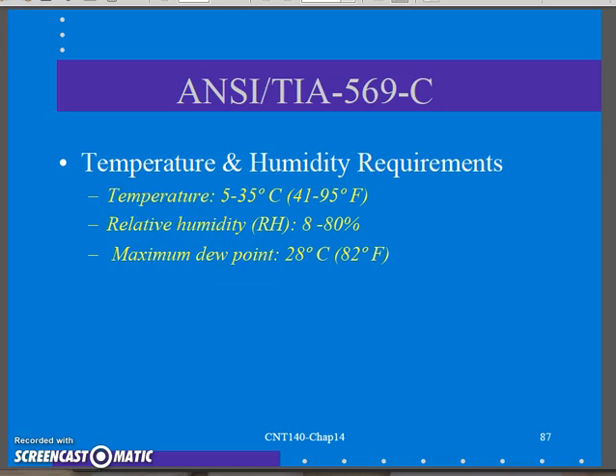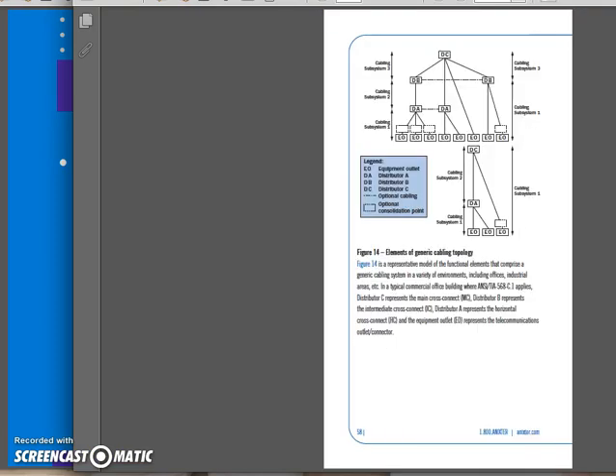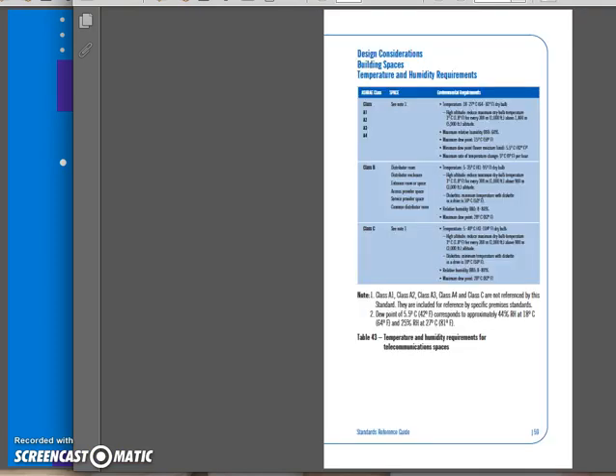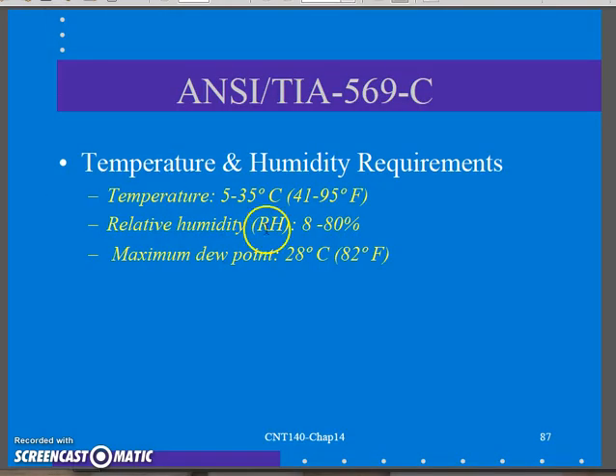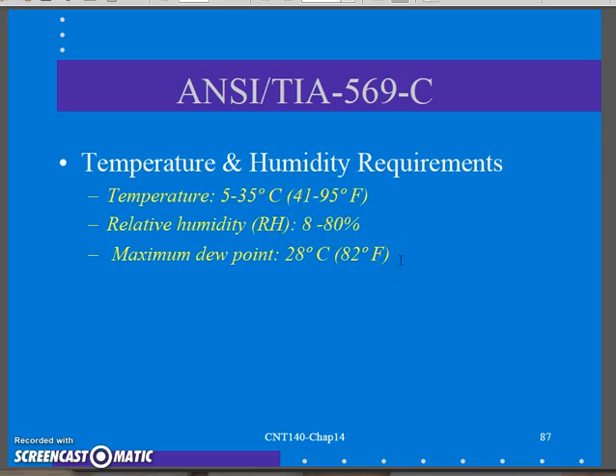One of the first things they mention in the standard is temperature and humidity requirements. Obviously, if equipment is too hot it's going to fail and shut down, so we need cooling in there. If it's too humid, things are going to rust. If it's not humid enough, things are going to have lots of static electricity and short out. They specify ranges, and your closet should have climate control for this, and if it's a main closet, maybe backup systems for when the main one fails. This stuff should be engineered in.